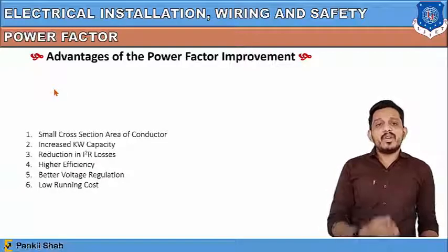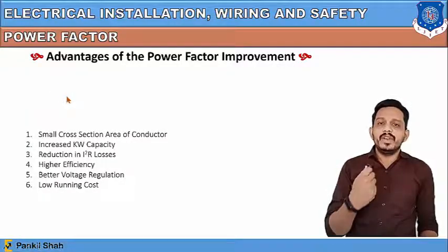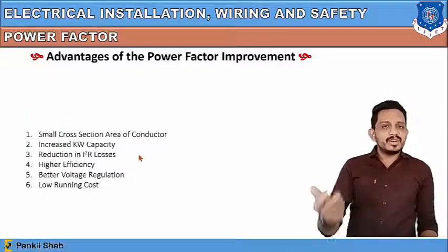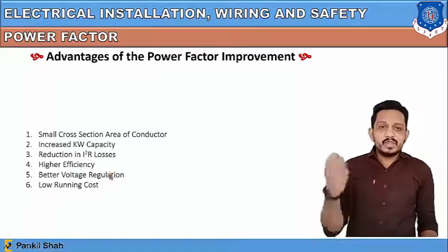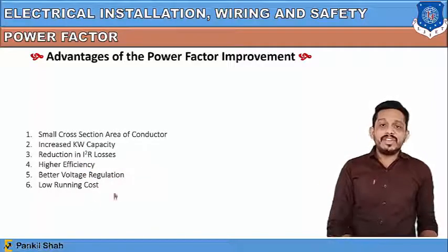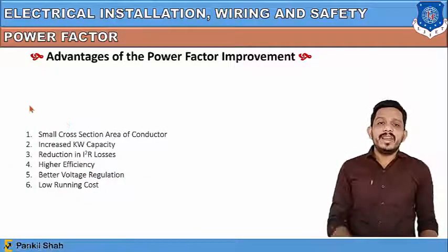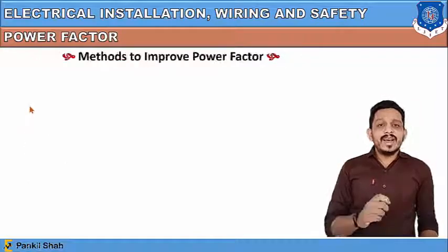Now let's say we improve the power factor. What are the advantages of improving the power factor? Small cross section of conductor, increased kW capacity, reduction in I square R losses, high efficiency, better voltage regulation, and low running cost. So these are the advantages. Now let's see the methods to improve the power factor.